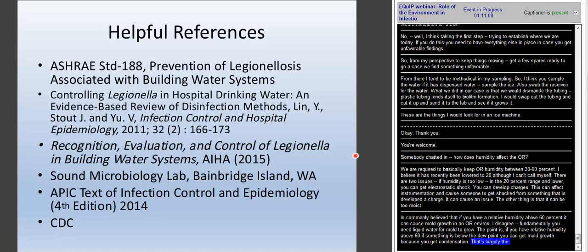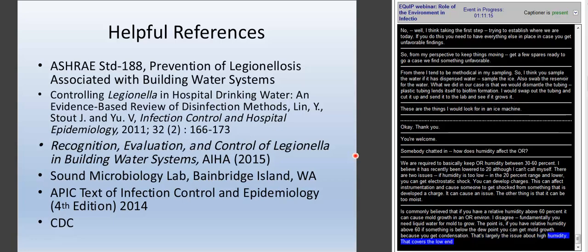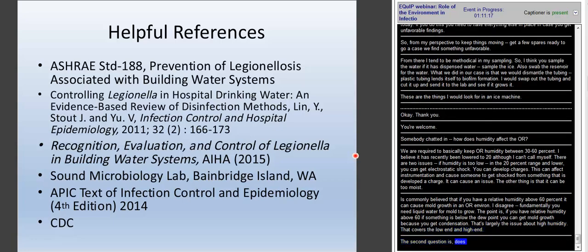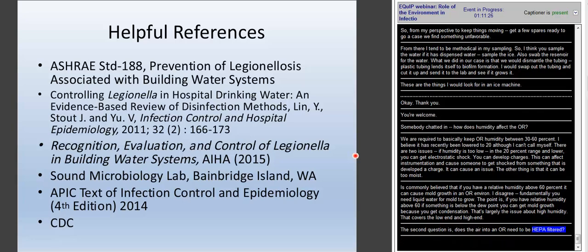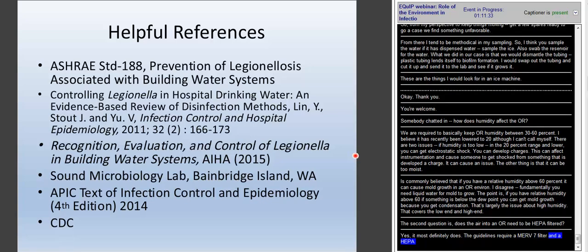The next question is, does the air into an OR need to be HEPA filtered? The answer is yes, it most definitely does. In the FGI guidelines, it requires a MERV 7 filter first and a HEPA filter afterward. So absolutely yes.